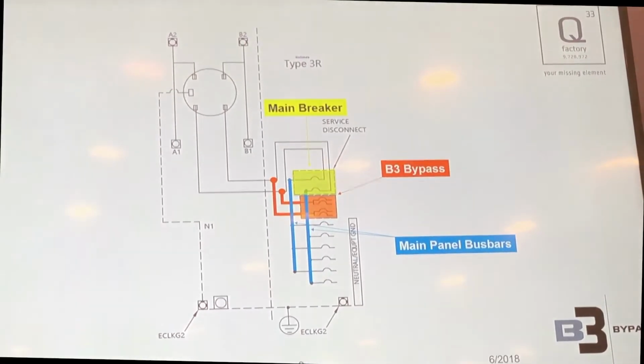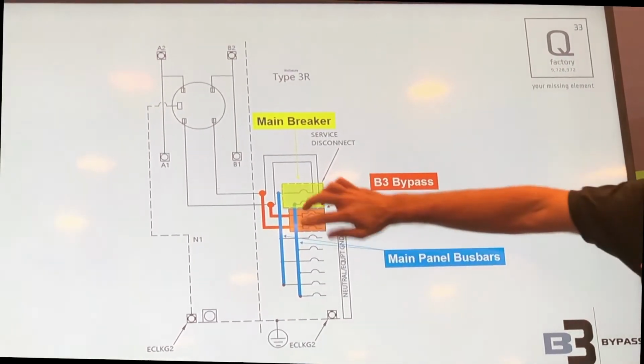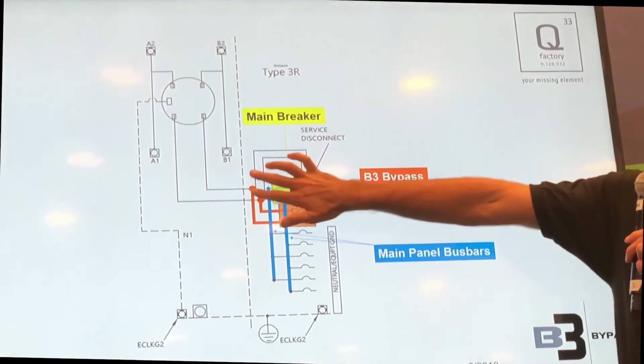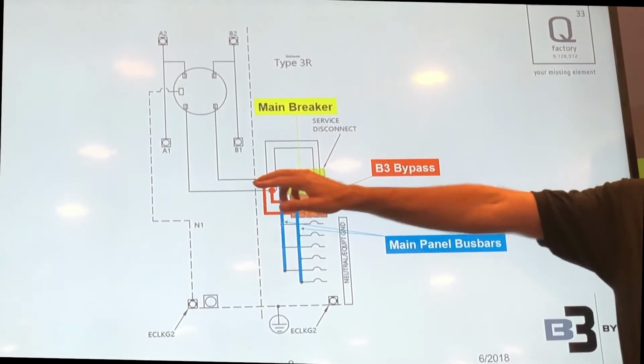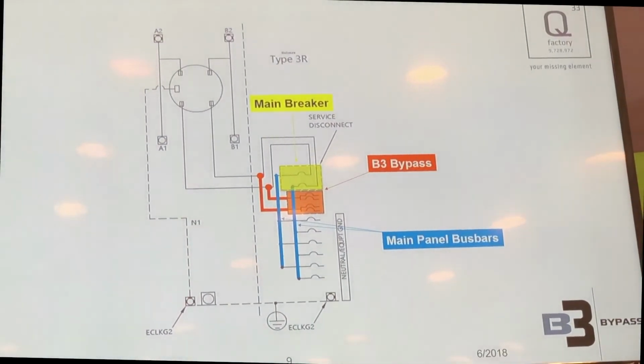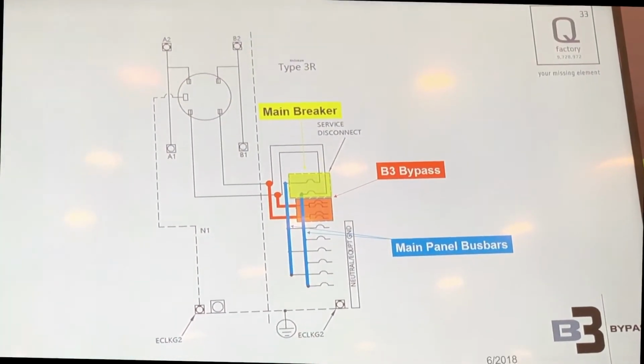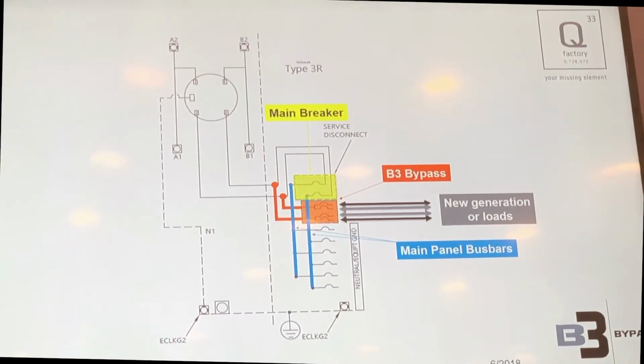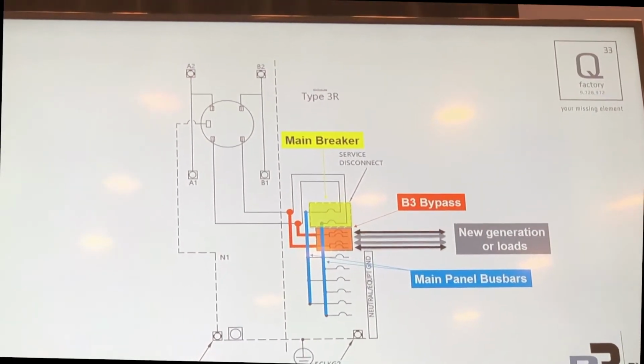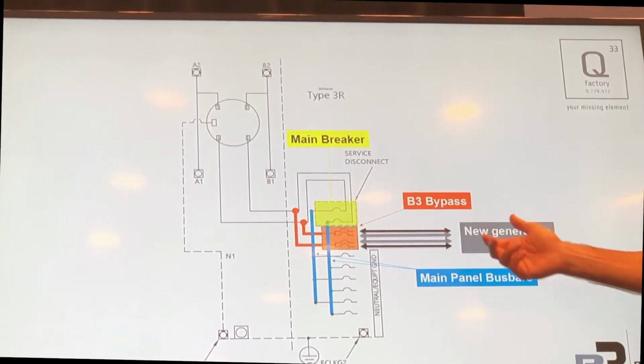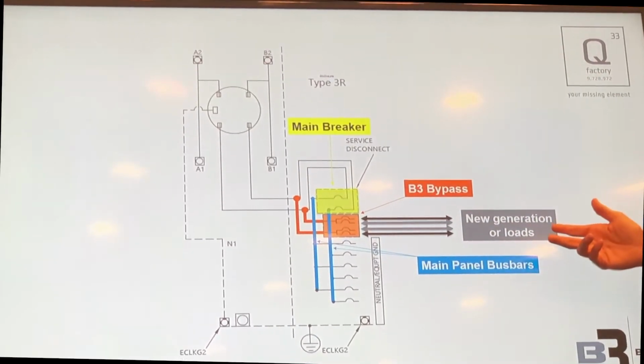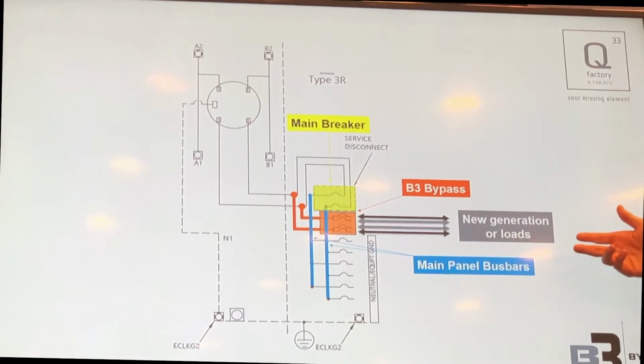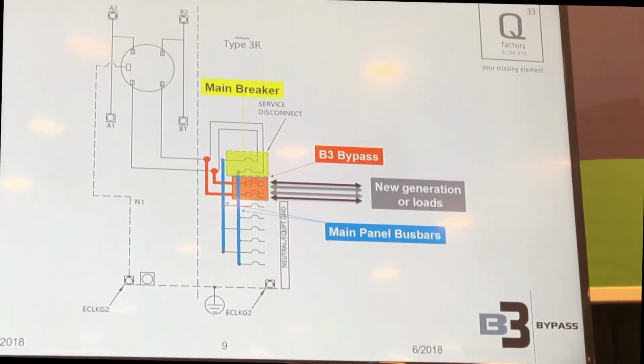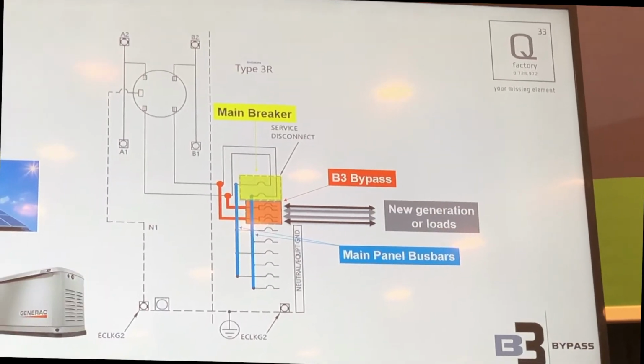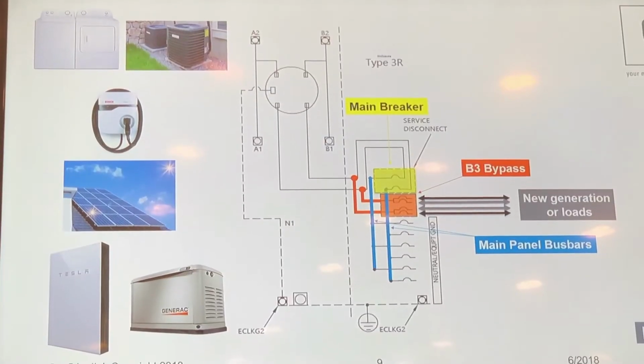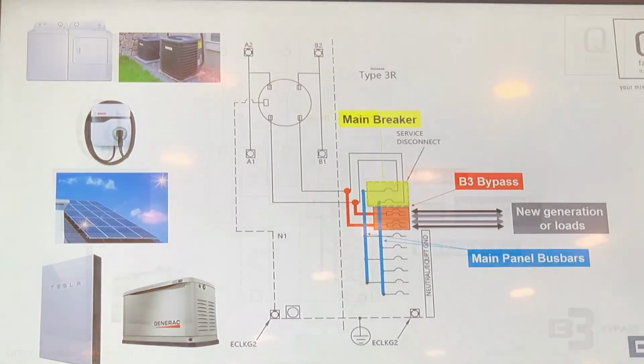Here's the B3 bypass, and as you can see, there's no contact to the bus bars here, so it's bypassing that. It's connecting directly to the feeder wires of the main breaker, thus the bus bar bypass. We can add up to 2 new loads or sources here, whether it's PV, battery storage, a traditional generator, or loads. And here are some examples of what could be added. This is the basic technical concept behind the product.